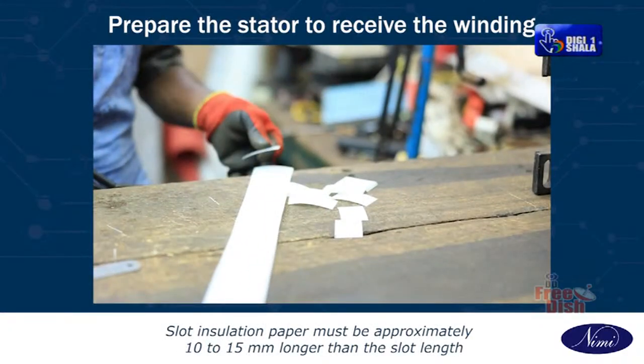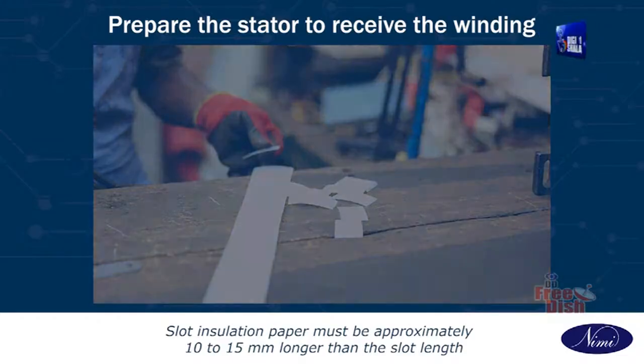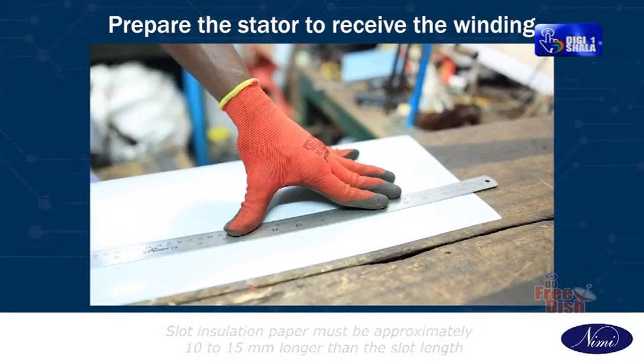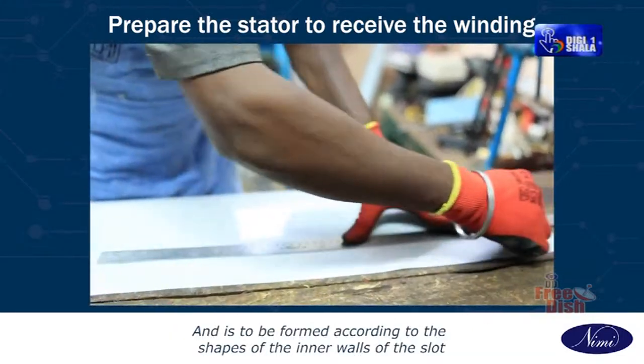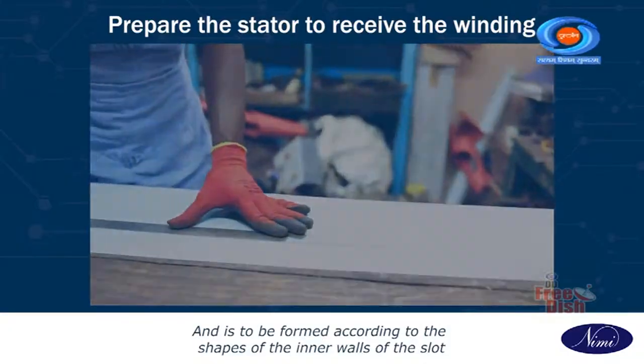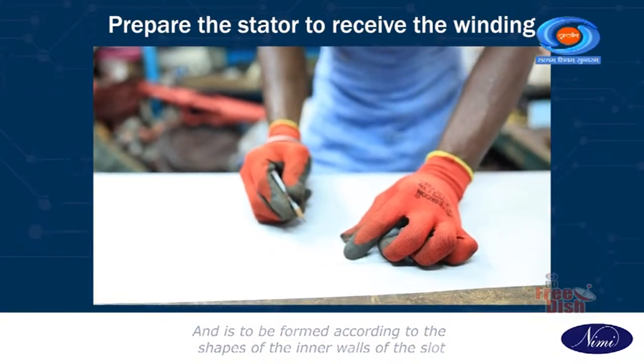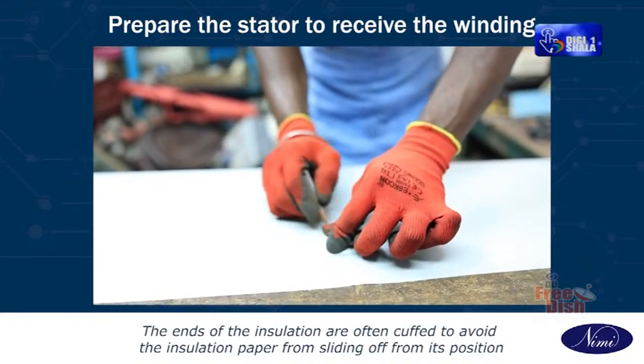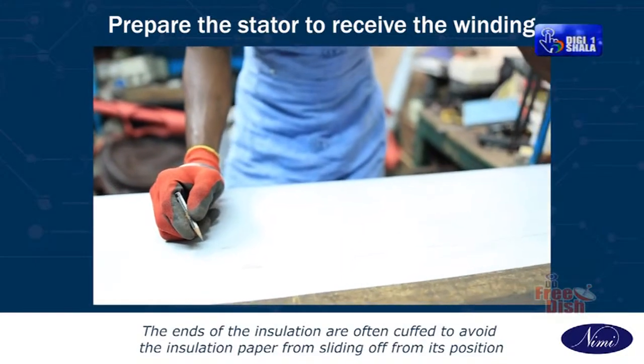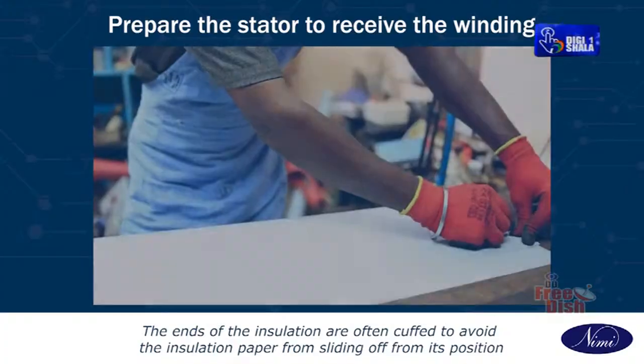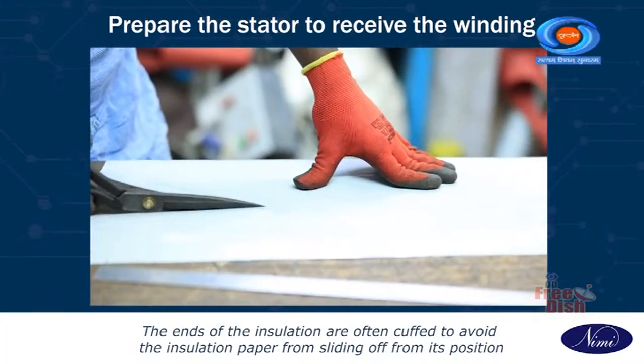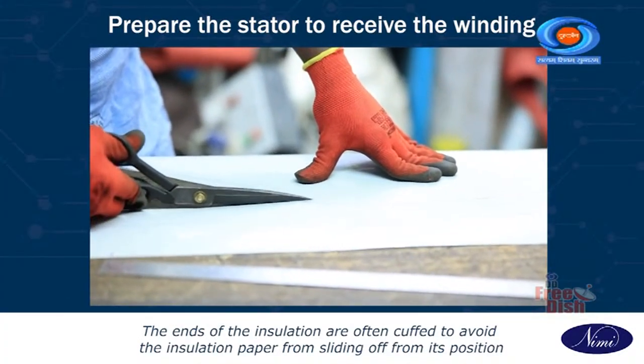Slot insulation paper must be approximately 10 to 15 mm longer than the slot length and is to be formed according to the shapes of the inner walls of the slot. The ends of the insulation are often cuffed to avoid the insulation paper from sliding off from its position. Task 3. Prepare coils.